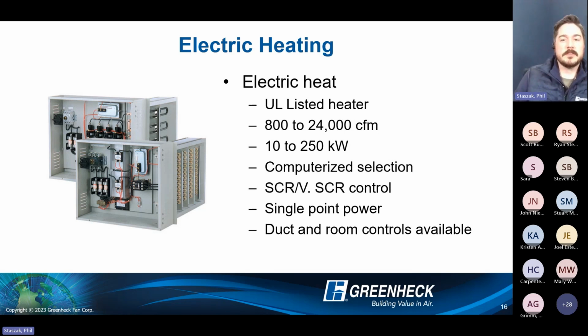Duct and room temperature control is available. These are SCR or vernier SCR controlled, so it's not just a toaster oven. It doesn't just turn on and give you full capacity. The reason there's the conversation with electrification is because of its efficiency. The efficiency on an electric heat is technically 100%. You can take every single usable volt going into it and convert that to heat; how clean that is, is where we can argue. And then again, cost standpoint as far as amperage, but technically it can be converted over to full usable heat. So depending on where you're actively working on jobs, because I know that you guys aren't limited to probably just Washington State, keep in mind that we do offer electric heating options. But if you guys are outside of the state, technically burning gas, if it's the lower cost option, is probably going to be the one that makes the most sense.